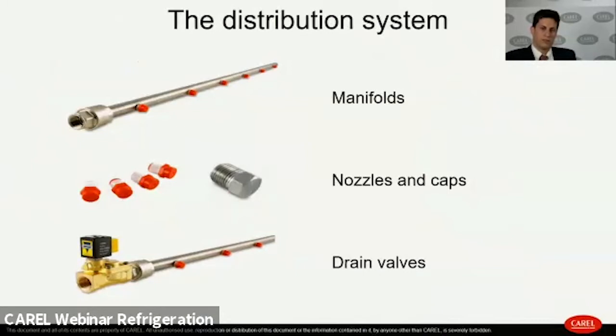Let's pass now to the distribution system. The distribution system is composed of a manifold with nozzles, cap, and valves. Manifolds are made of stainless steel and are available in different sizes in order to be flexibly mounted according to the dimension and the geometry of the gas cooler. We have 3 different sizes of nozzles, in order to combine the manifold size, manifold length, the number of holes where to install nozzles, and the nozzle size, and fit perfectly the geometry constraints of the coil and the actual request in terms of liters per hour of sprayed water.